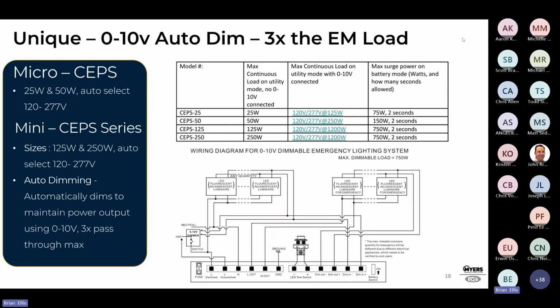You don't have to pipe two sets of wires. It's just emergency hot and neutral and 0 to 10. So now we've started to save some extra wiring and installation for the contractor. And honestly, probably a better outcome. We have even illumination. So one question you might have is, how much can I put on this? So we kind of wrote in here 3 times the EM load, right? So don't really want to go above 75 watts on the 25, 150 on the 50, 750 on the 250.